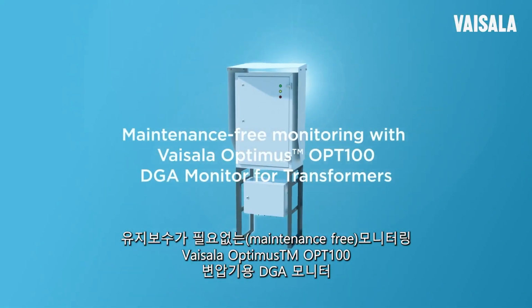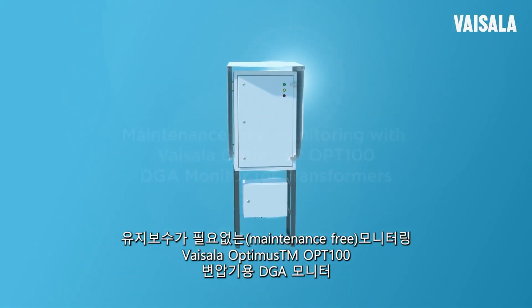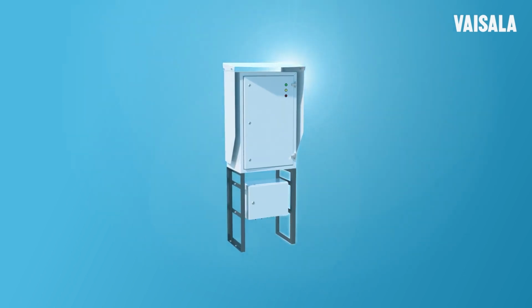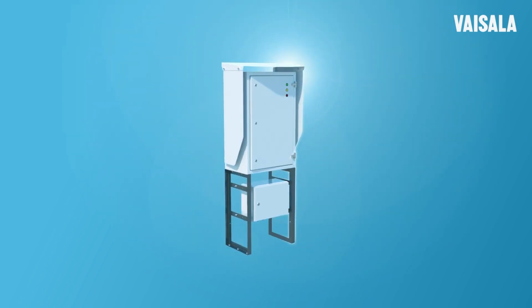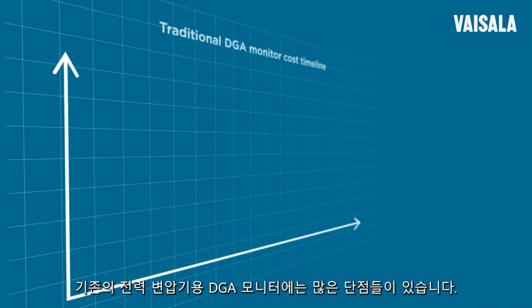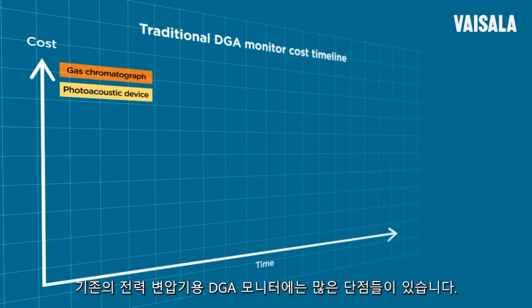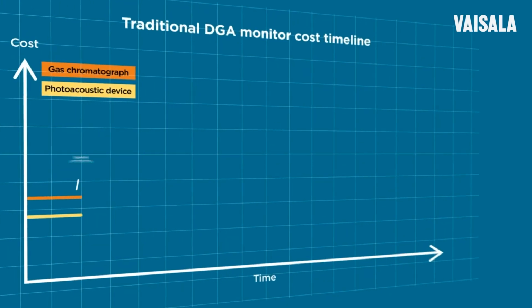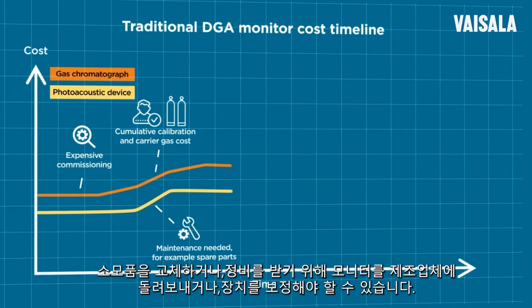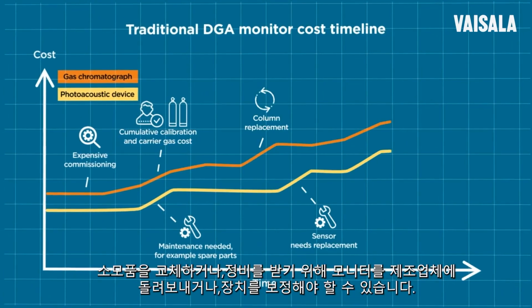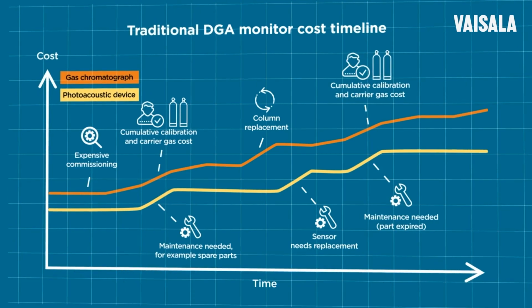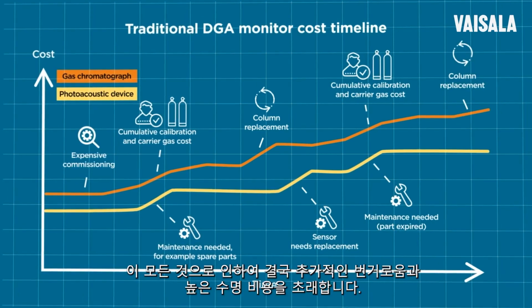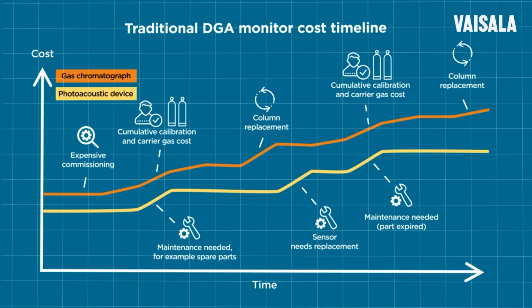Maintenance-free monitoring with the Vaisala Optimus OPT100 DGA monitor. Traditional DGA monitors for power transformers have many drawbacks. You may need to replace consumables, send the monitor back to the manufacturer for maintenance, or calibrate the device. All of this adds up to extra hassle and higher lifetime costs.